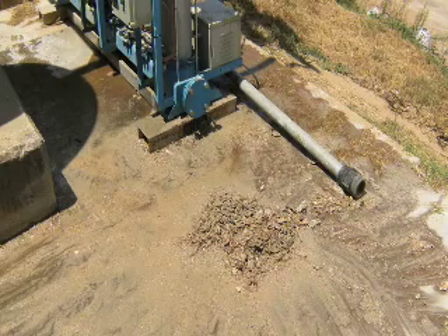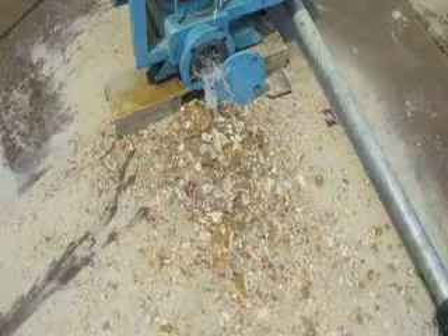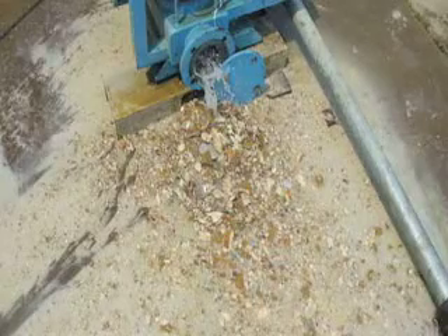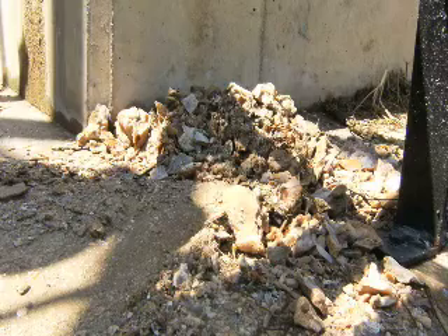The WESU system scales the carbonates in their reactor, in their system, and not on the piping of the cooling system. So you force the scaling to occur in a place where you can control it, and not in a place where you don't want it to scale. And by removing it, you can recycle your cooling water for a longer period of time, so you don't have to bleed off to prevent too high a buildup of scaling.